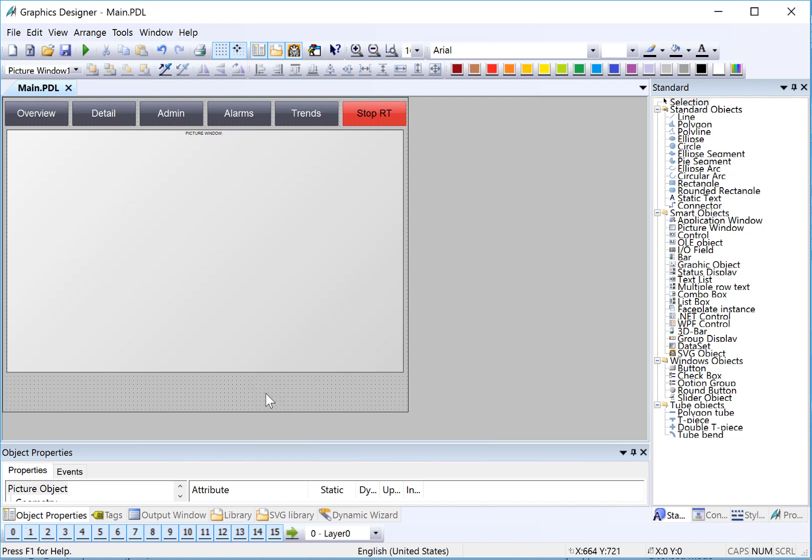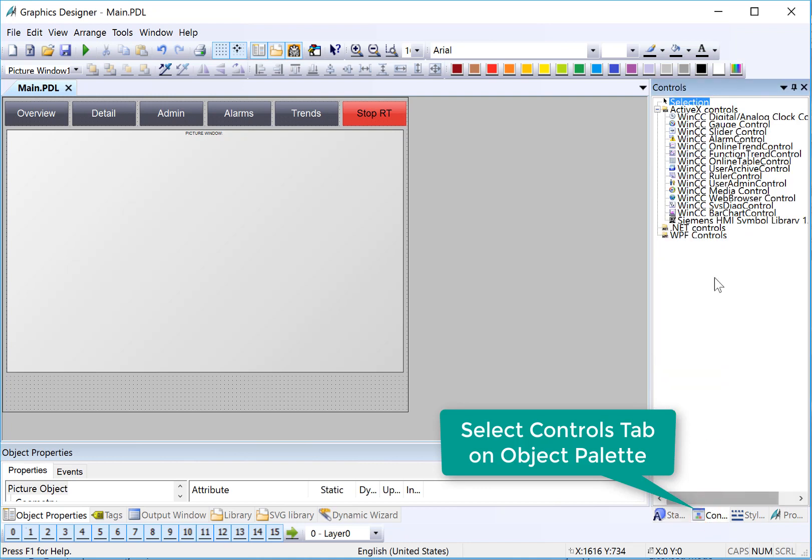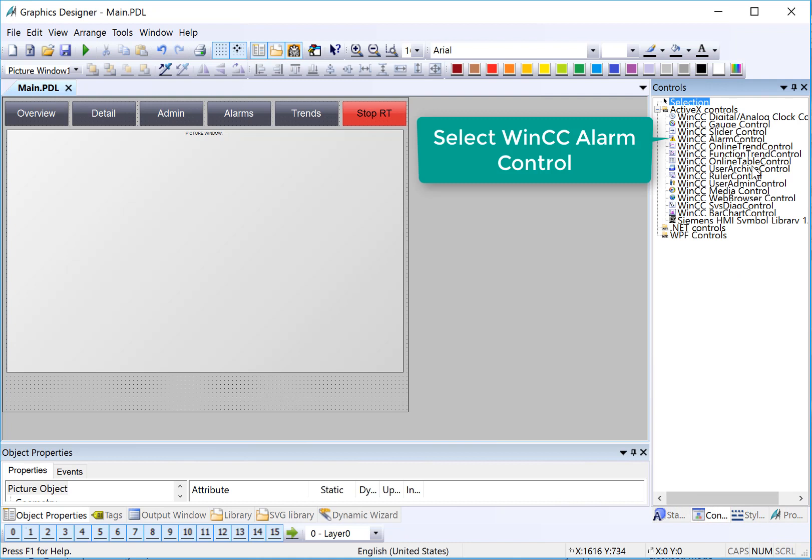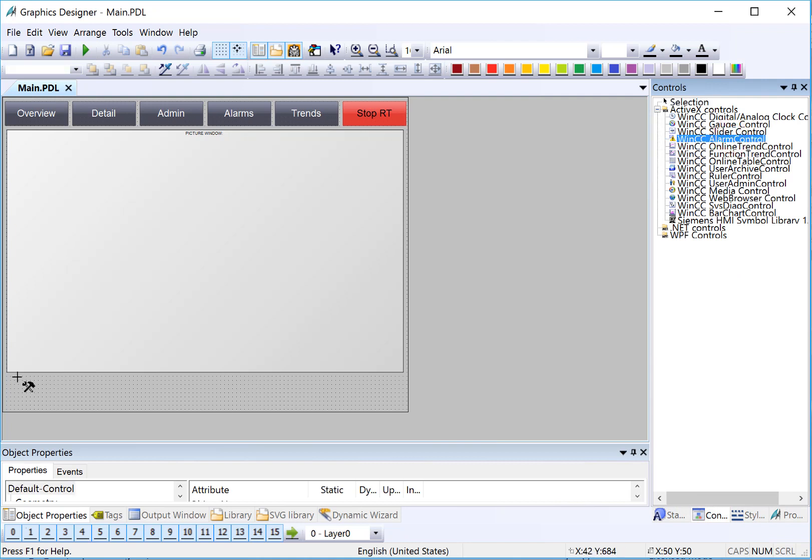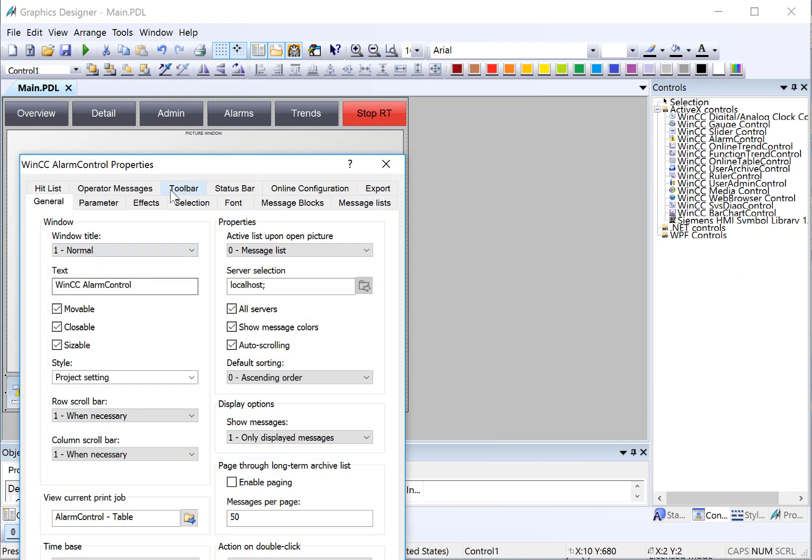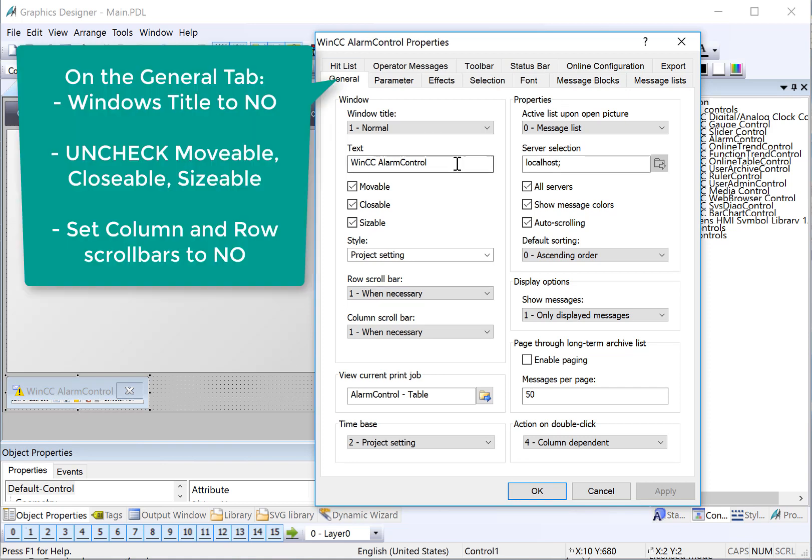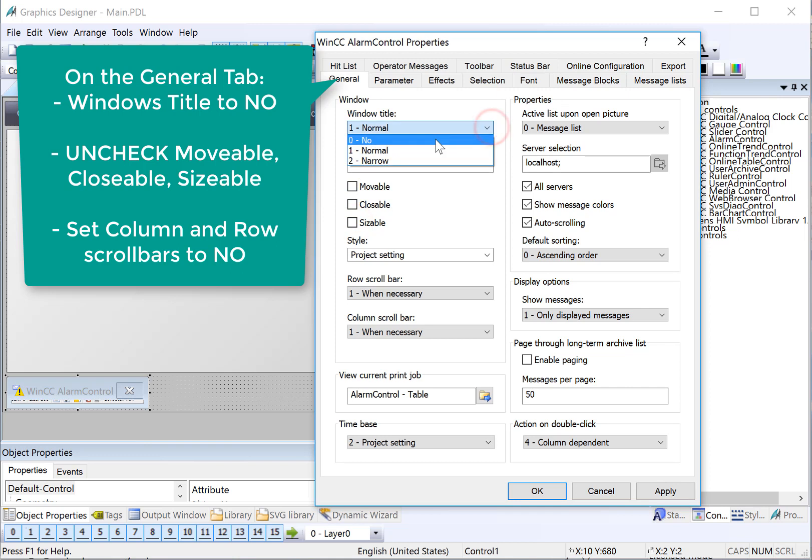Next, I'm going to place the alarm banner. The alarm banner is just going to be a simple banner that shows us active alarms. And then we'll have an alarm overview page that shows us all the details. In order to get the alarm banner, I'm going to need to go to the controls palette down here in the lower right-hand corner. I'll highlight that. I will find my WinCC alarm control. And I'm just going to drag it out. Now, when I drag it out, it is going to show me the properties. And there's, of course, a lot of stuff on here, but we're going to whittle this down so that it's really only showing date, time, and the alarm message. So on the general tab, I am going to turn off movable, closeable, and sizable. And I'm going to turn off the title.